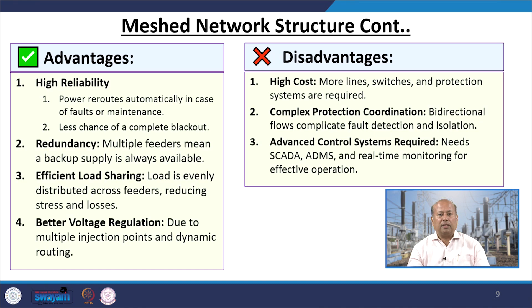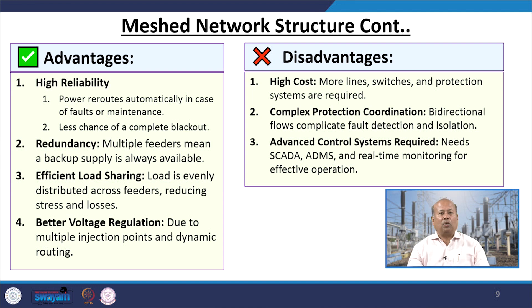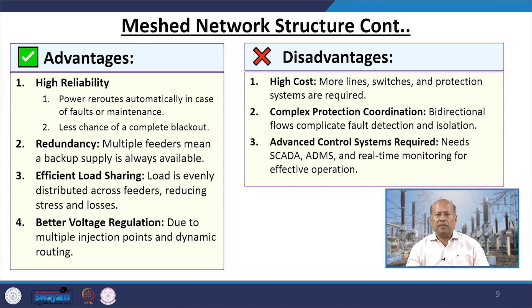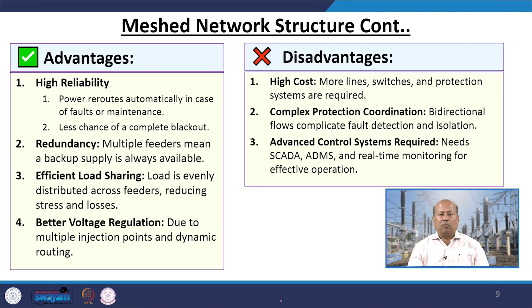The advantages of meshed network structure are: high reliability — power reroutes automatically in case of faults or maintenance with less chance of a complete blackout; redundancy — multiple feeders mean backup supply is always available; efficient load sharing — load is evenly distributed across feeders, reducing stress and losses; and better voltage regulation due to multiple injection points and dynamic routing. The disadvantages include high cost — more lines, switches, and protection systems are required; complex protection coordination — bidirectional flows complicate fault detection and isolation; and complex control systems such as SCADA, ADMS, and real-time monitoring are required for effective operation.